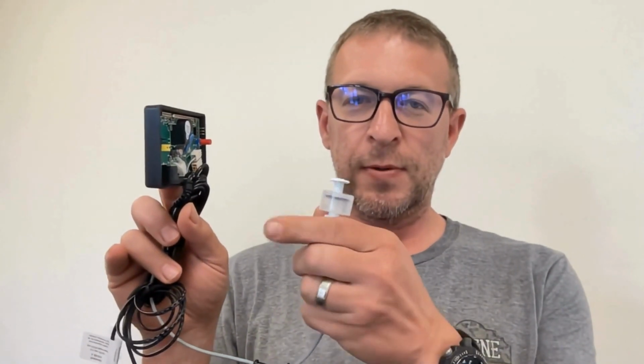First thing we should discuss is just a general overview of Osmolator function, and the 2 most common error lights that are just normal. Too high. Too high happens when the float switch is raised. It can also happen if the float switch is affected by a magnet. This is a magnetic switch. The black ring in the bobber is a magnet, and it's flipping a switch inside the post. If it's too close to another magnet, say you're using the optional float switch magnet, and then you have the optic sensor on the optic sensor magnet, or the magnet that holds both sensors, and those are too close, that can trigger this float. It can also prevent the float from working, so we always want to manually check that that cycles and works properly.